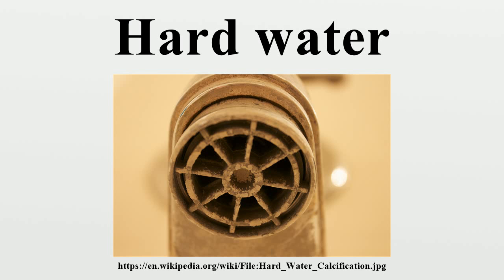Where softening is practiced, it is often recommended to soften only the water sent to domestic hot water systems so as to prevent or delay inefficiencies and damage due to scale formation in water heaters. A common method for water softening involves the use of ion exchange resins, which replace ions like Ca²⁺ by twice the number of monovalent cations such as sodium or potassium ions. Washing soda has long been used as a water softener for domestic laundry, in conjunction with the usual soap or detergent.